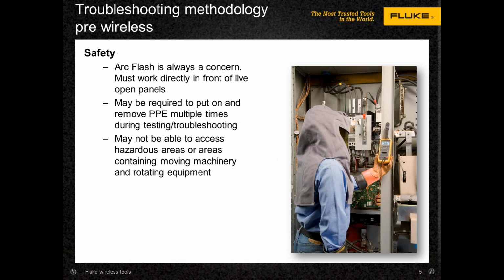Basically, safety is a big play with the wireless thing because today and in years past, arc flash is always a concern. Anytime you're making measurements in an energized panel, there's a chance for an accident, a slip, where the probe tips get shorted together, and a phase to phase or phase to ground short happens, and then you have issues. Where the wireless comes into play is that you can install a module, use some alligator clips, hook up to the measurement points you want, and then back away from the panel, energize or flip your control, and get out of the way.